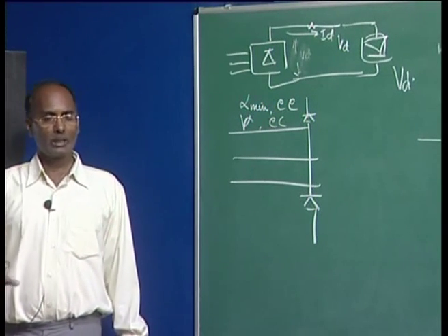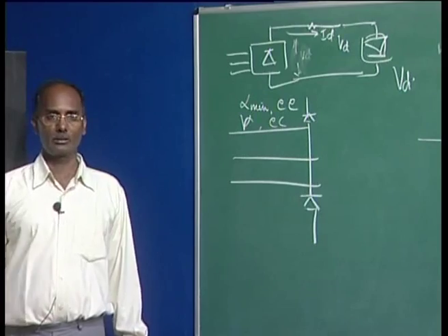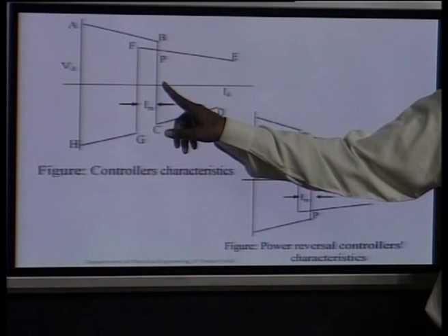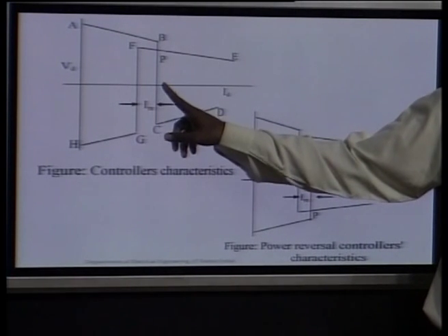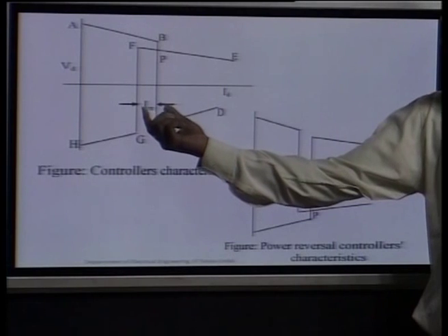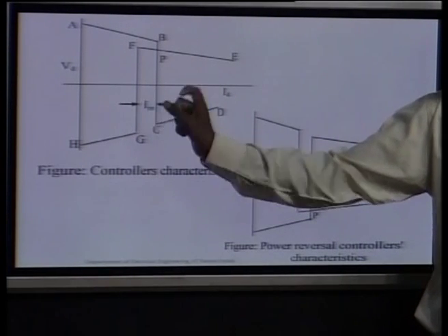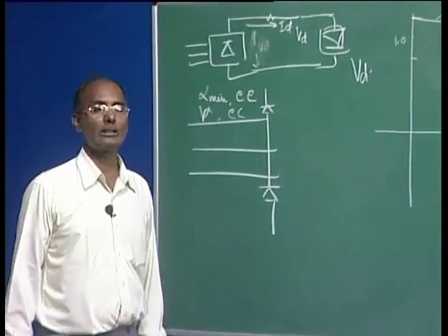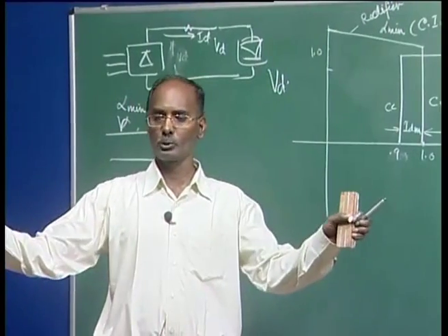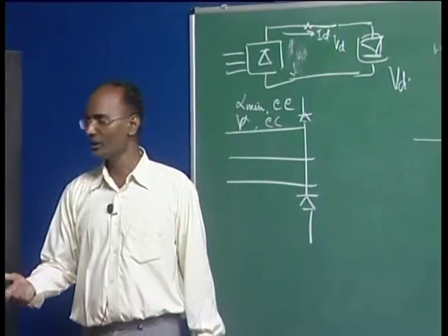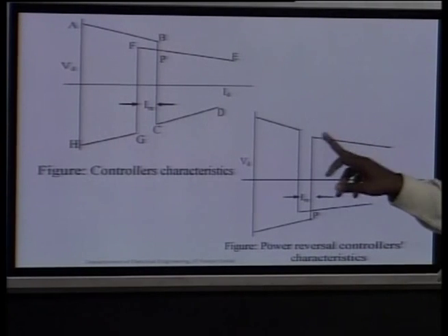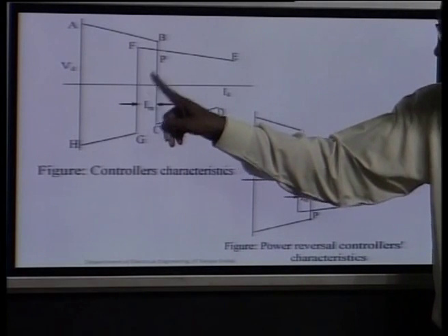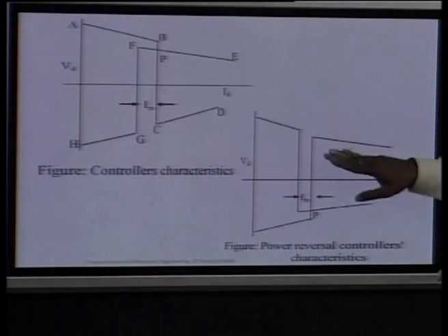So what we do, we never change the characteristic, only we change the margin. You can see here the rectifier in the normal case was rated at the ID, which is rated current. Now there was some margin here, IDM, IM here it is written. Now what we do, we change it here in this mode. Because this is only 10%, so a 10% change in setting is very easily possible. If you are going to change a huge amount, it is not possible, but 10% you can change the reference. So now you can see here, this current is going to be increased. Earlier this current was less than your rectifier end current. Now this is coming this side and this is going this side, and then an intersection point is possible.